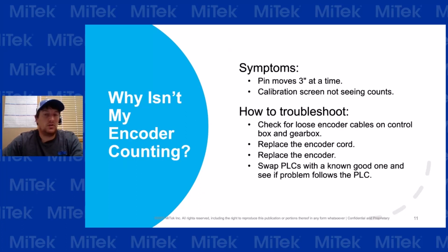First, I would start with the encoder cord, check to see if it's tight to the control box, check to see if it's tight to the gearbox. If that appears to be tight, I would change out that encoder cord. It's the easiest thing to do. You should have a spare one that we send with each spare parts box, and plug it into the encoder, plug it in the gearbox or control box, and see if you have any movement. Then if it's moving 3 inches at a time again still, then you need to swap out your encoder.